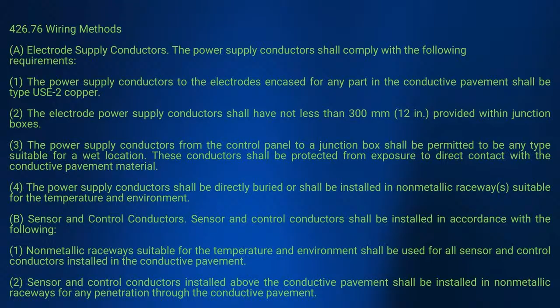And a good example of one here is you got these supply conductors that can be directly buried, or if you're going to install them in a raceway, guess what type you have to install it in? You can't install it in metallic. It has to be a non-metallic raceway that's suitable for the temperature and environment. And then it gets into your sensors and control conductors. And once again, what does it tell you? Where you're using that for all that sensor and control conductors, you need to install that in what? A non-metallic raceway.